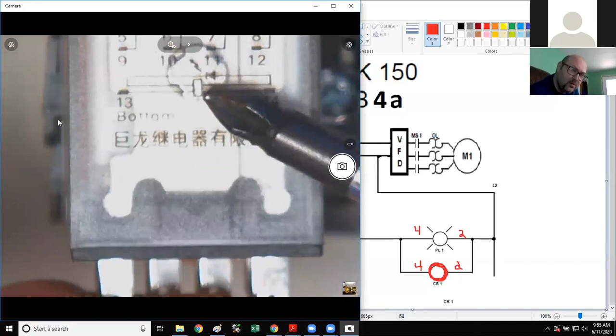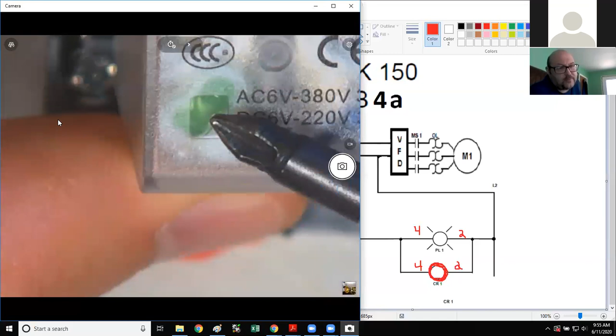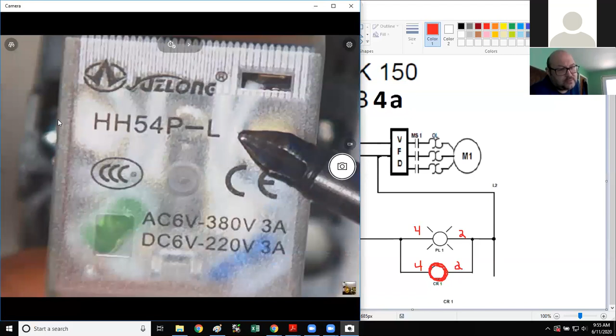On the diagram, it's also showing this little LED right up here. All that's saying is that when the coil is energized, you'll get an indication on this little LED light on the front, saying this thing has changed the state of all its contacts. When the coil is energized, it creates an electromagnetic field, which changes the state of these contacts.